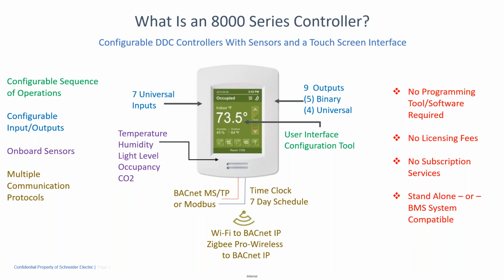On the device itself, it's got a humidity sensor and a temperature sensor. It has a light level sensor, so the screen will dim down when the room gets dark, and it can also have a built-in occupancy sensor. Along with that are 7 universal inputs that are configurable, as well as 9 outputs. 5 of them are binary and 4 of them are universal. So it's quite a powerful little controller, all in one little package. Again, about the size of a thermostat, right?